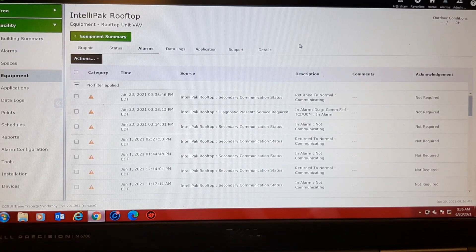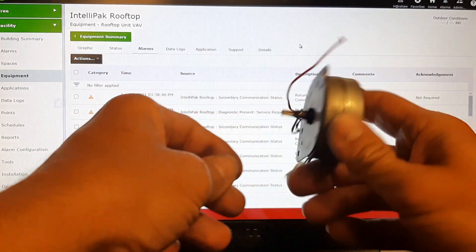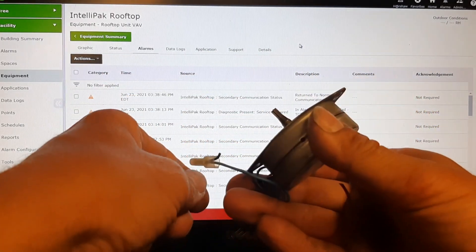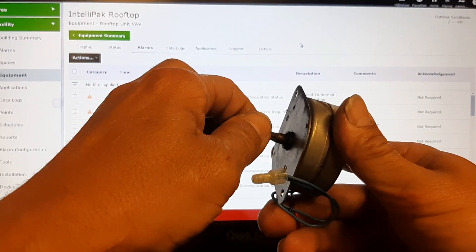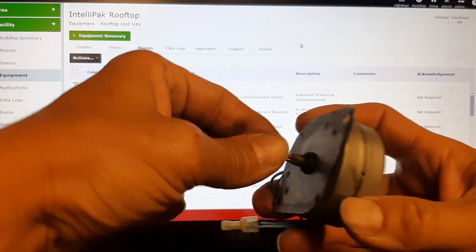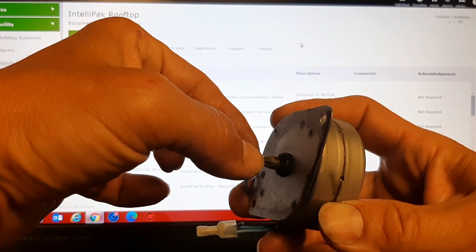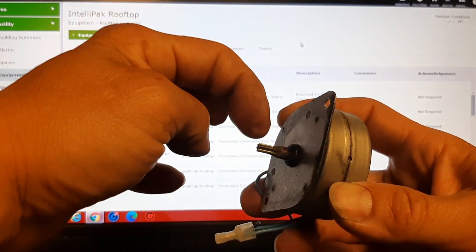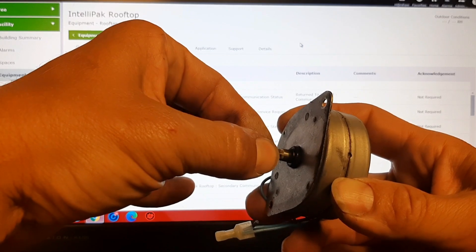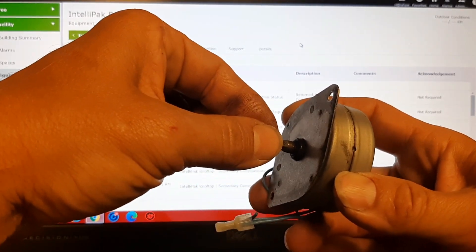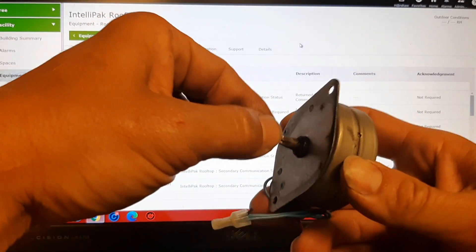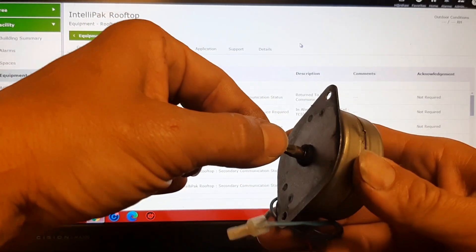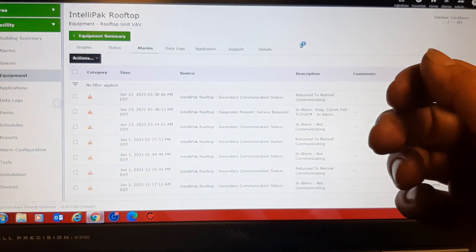If you guys have ever seen one of these guys, this is the actuators on the old VAV boxes. And it rotates to open and close the damper. You see the movement in that bearing. You've got gears that fit inside there, and as it rotates, it rotates it open. When the bearings are failed, they sound like a hamster in a wheel or something, and then they won't actually turn.